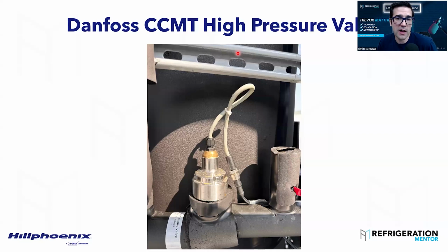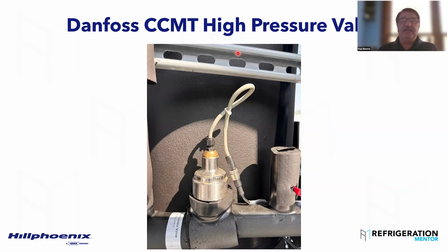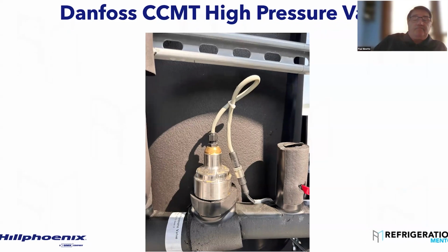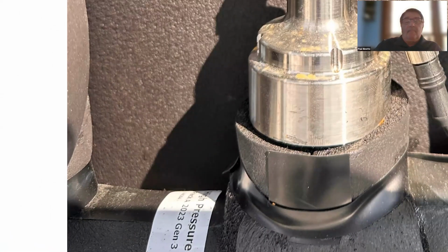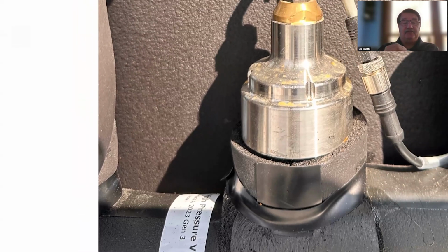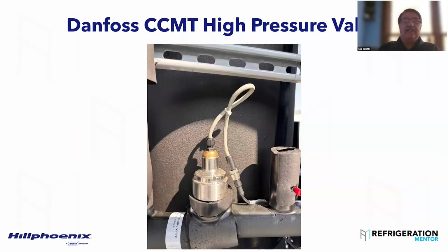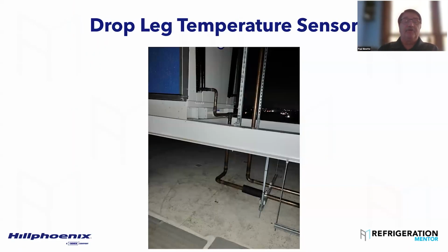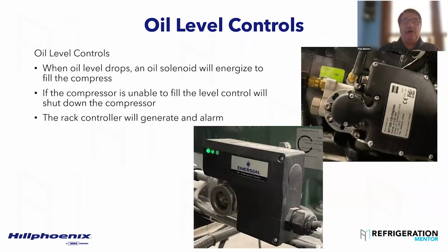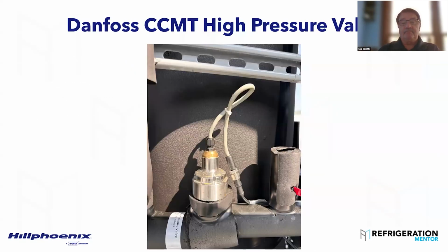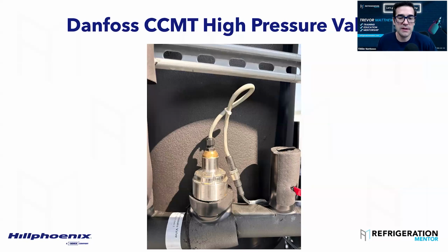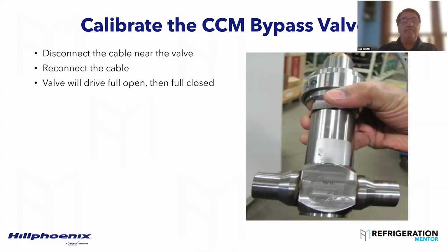So this is the flash gas bypass valve. I threw a high pressure valve in there. I thought it was a CCMT, but this is a flash gas bypass valve. This one here. Yeah, this is CCM. That's actually incorrect. That's a CCM. The T we would use on the high pressure side. The difference being is the CCM is literally a straight through valve, where the CCMT is in essence a TXV for creating a pressure differential. So it'll be a come in the top, blow out the bottom valve. Okay, perfect. So that's my mistake on the slide there. So no problem at all. We all make mistakes. That's how we learn.